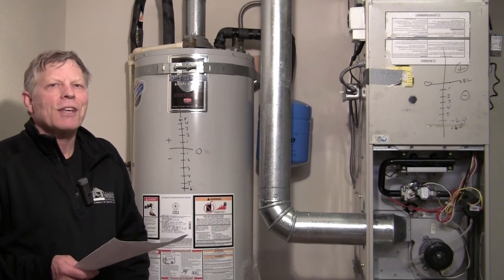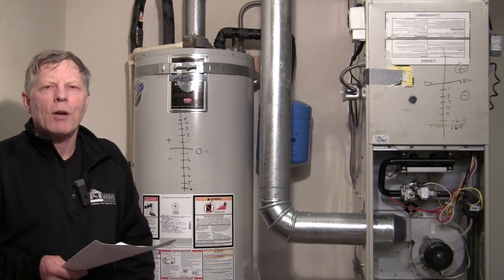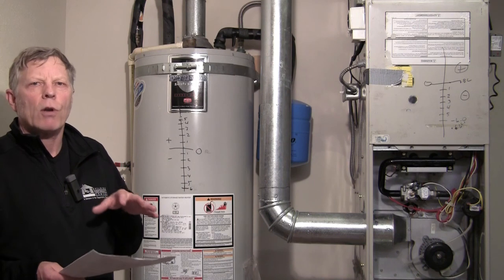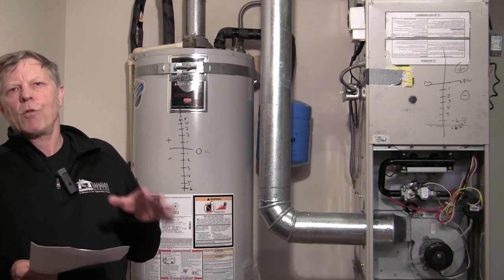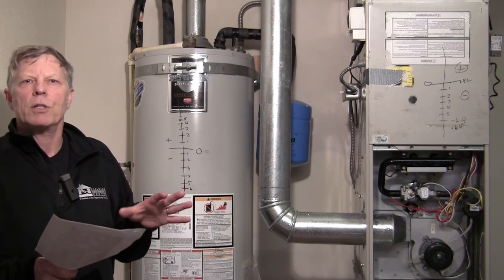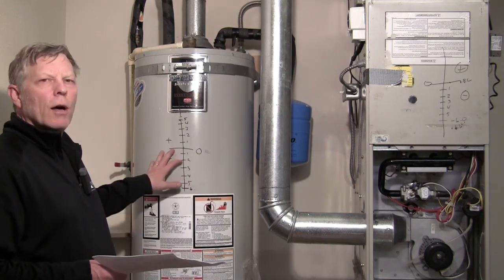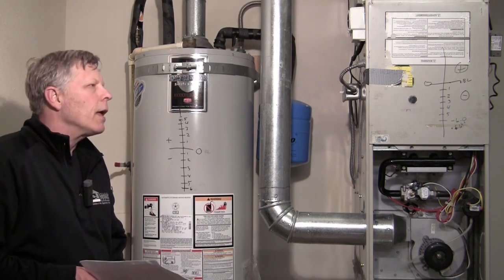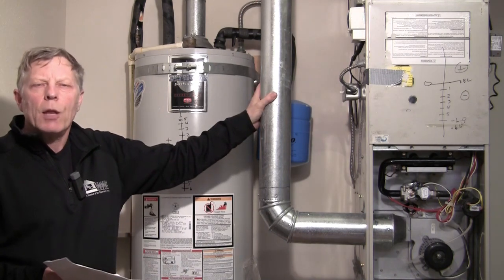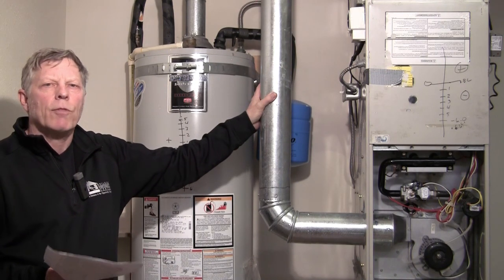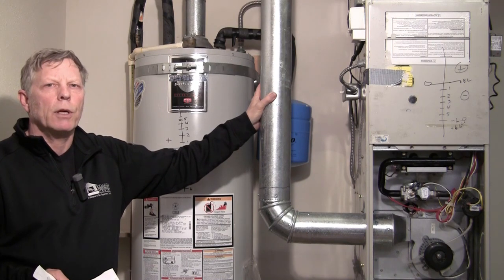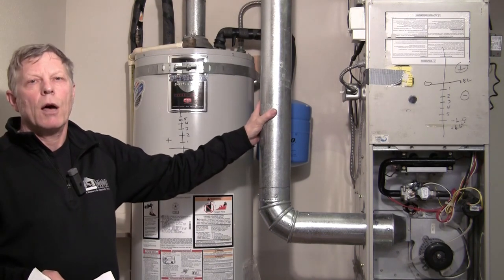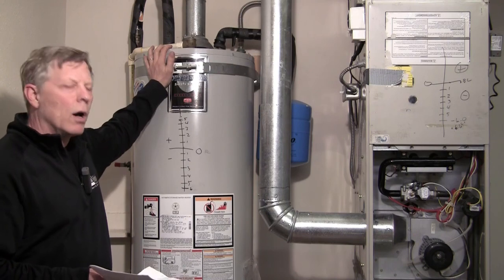Okay, we finished up our worst case depressurization and we got it to about negative 7.6, I think. I turned all those fans off for a moment so I could talk about where we go next on the form, and then we'll get back into worst case before we start our CO spillage test. But what we have here is a shared venting situation. We got a category 1 water heater with a draft hood and a category 1 80% induced draft furnace, both on the same vent, so they both get tested for spillage. We'll test for spillage for the water heater at the draft hood, and we'll also test for spillage for the furnace at the draft hood of the water heater, okay?